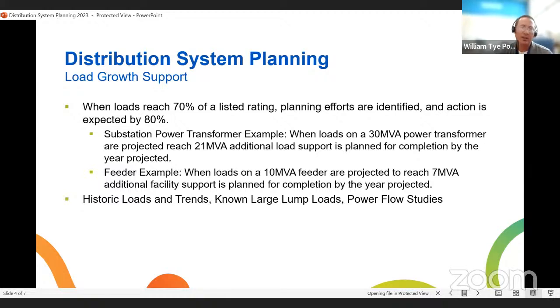At the feeder level, when loads on a 10 MVA feeder are projected to reach 7 MVA, then we have additional facility support planned by that projected year. Now this doesn't mean that we necessarily need new facilities - it just means that we could perform different types of system switching activities or other types of activities to free up that capacity at that point.